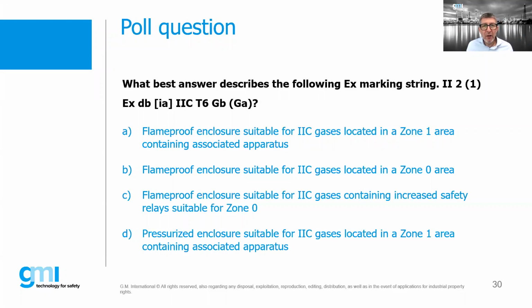So what is it? A flame-proof enclosure suitable for IIC gases located in zone 1 that contains associated apparatus? A flame-proof enclosure suitable for IIC gases located in zone 0? A flame-proof enclosure suitable for IIC gases containing increased safety relays suitable for zone 0, or a pressurized enclosure, and so on. Well, I would say the last one is easy to see: it says pressurized. Pressurized is Ex p. That's right. Yeah, I see an Ex d here. D is explosion proof or flame proof. So definitely one of answers A, B, and C.